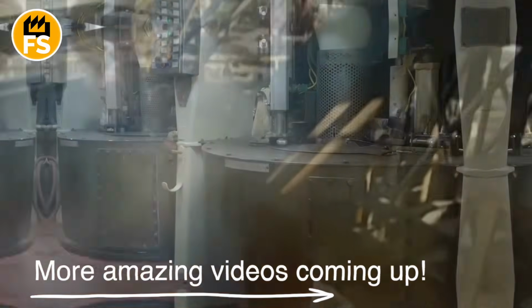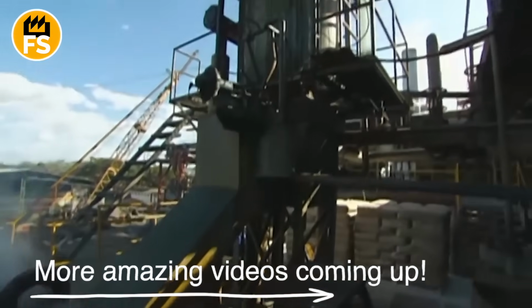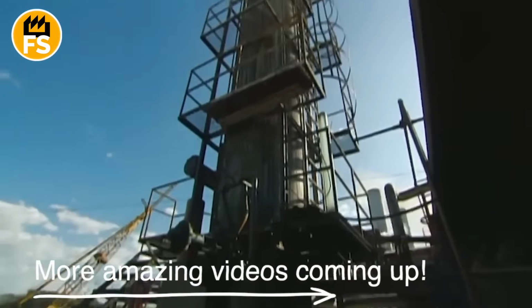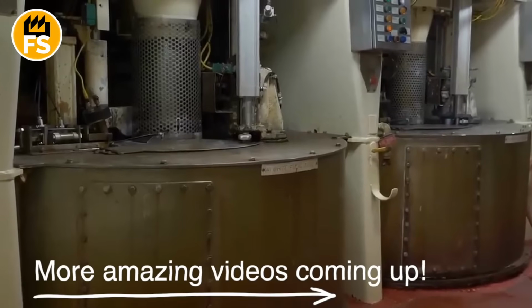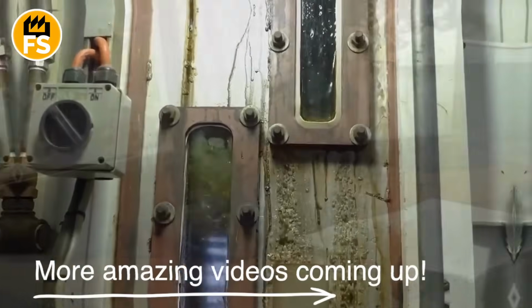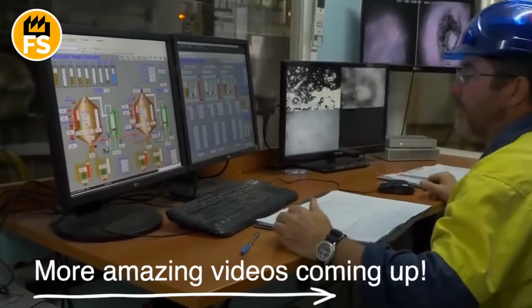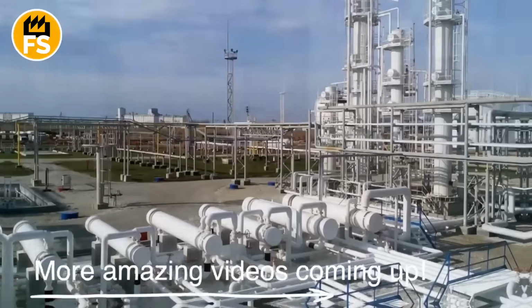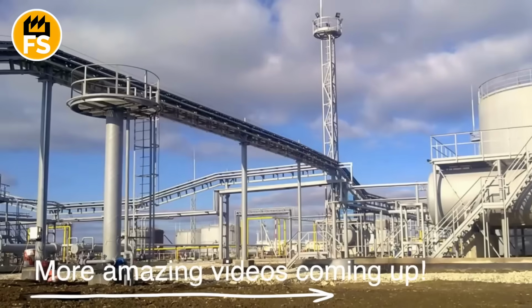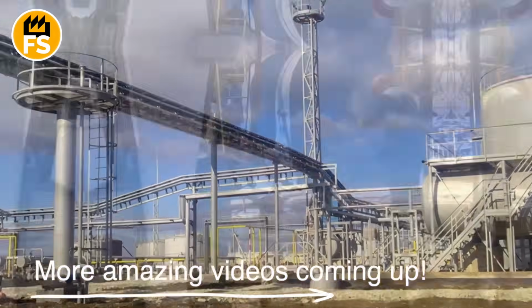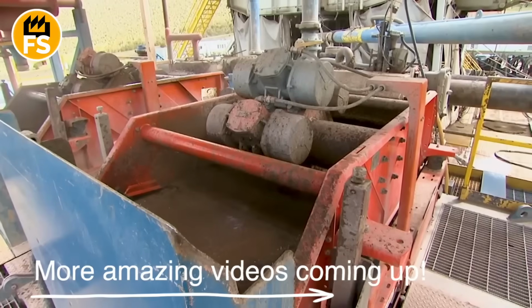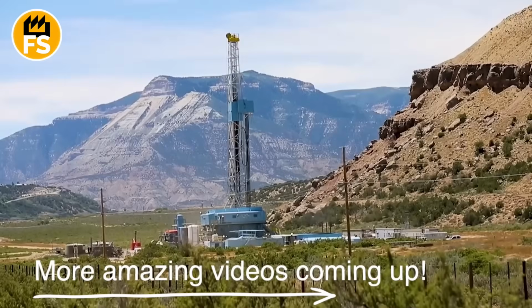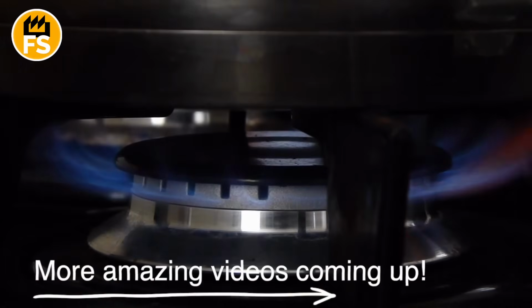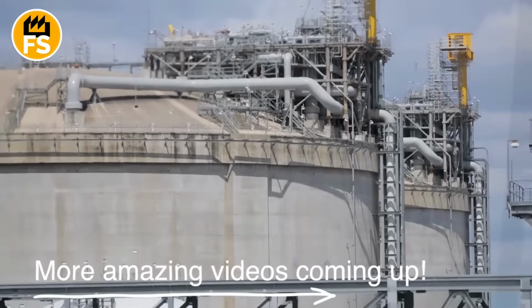First, the gas is compressed, meaning it's made very dense, like when you squeeze the air in a balloon. It becomes smaller in volume, but warmer. Then, this warm compressed gas is passed through special coolers. After that, the gas is passed through special devices, expanders, which allow the gas to expand and cool down even more, like when you let air out of a balloon and it becomes cold. Thanks to this, the gas cools down significantly, to about -260 degrees Fahrenheit.